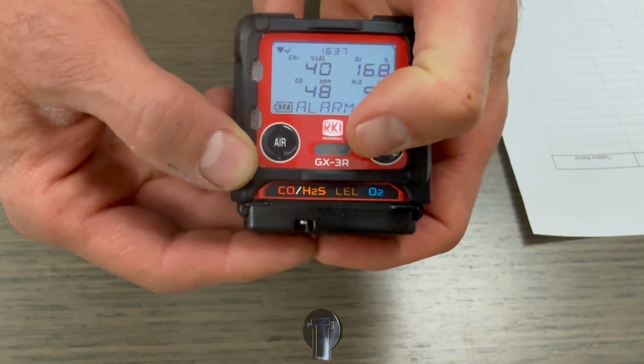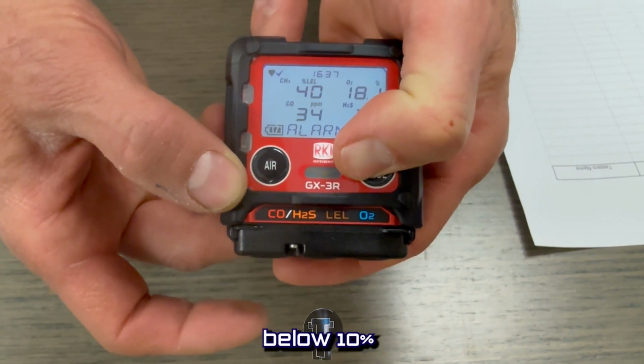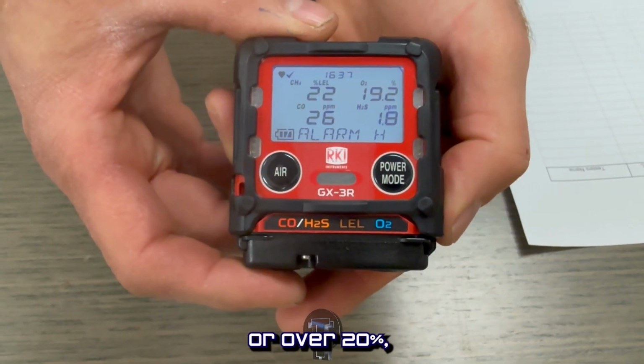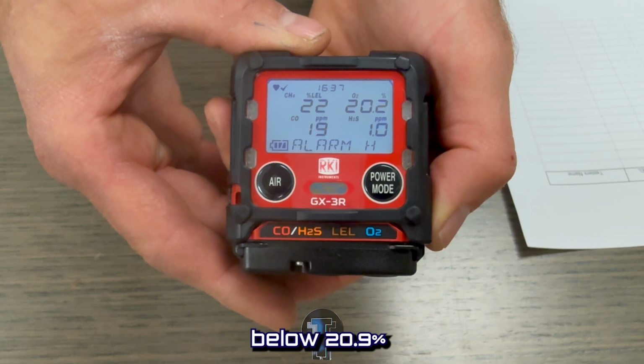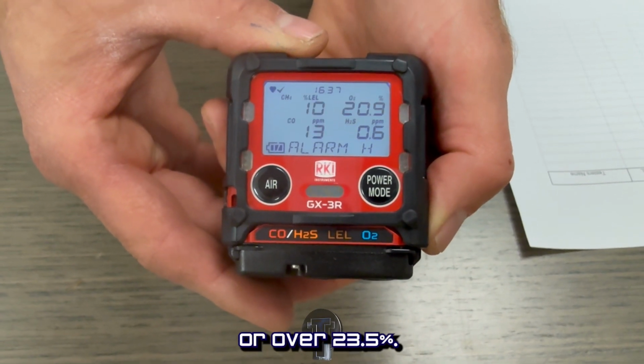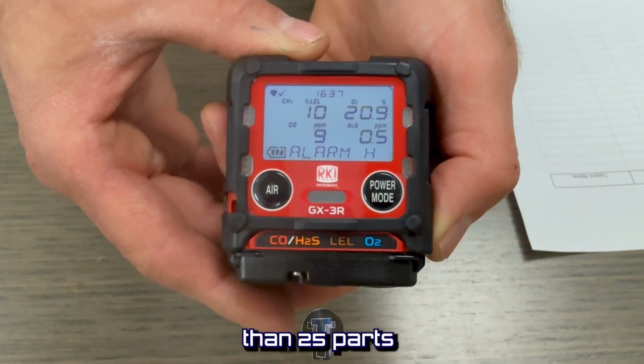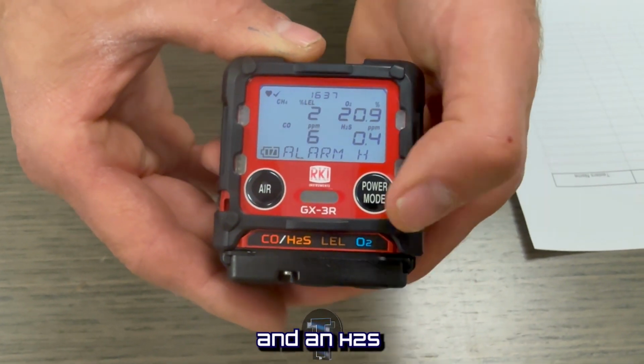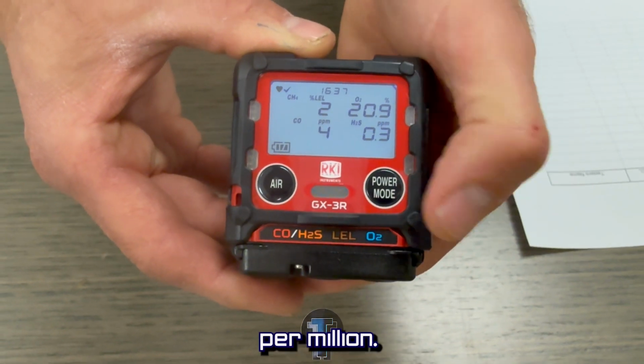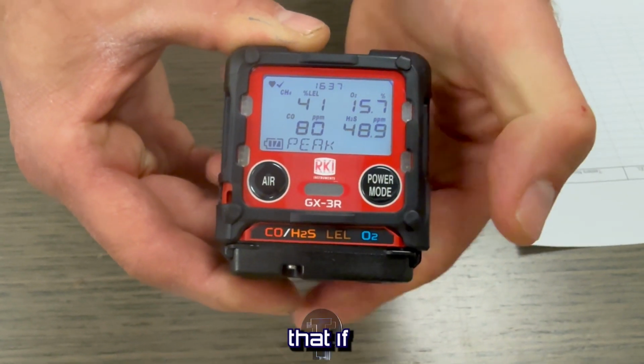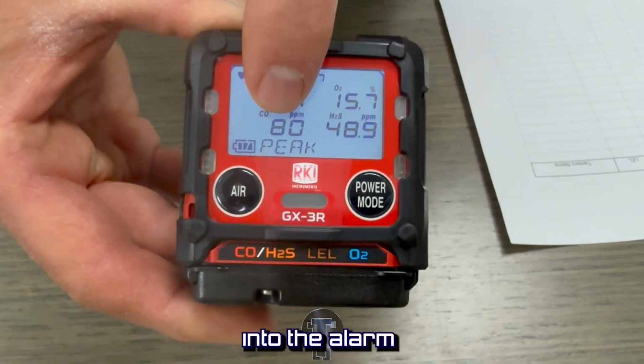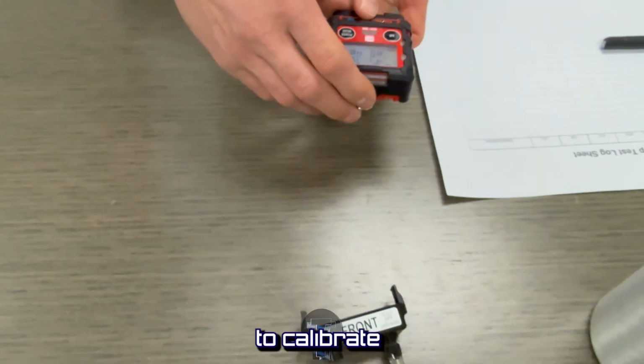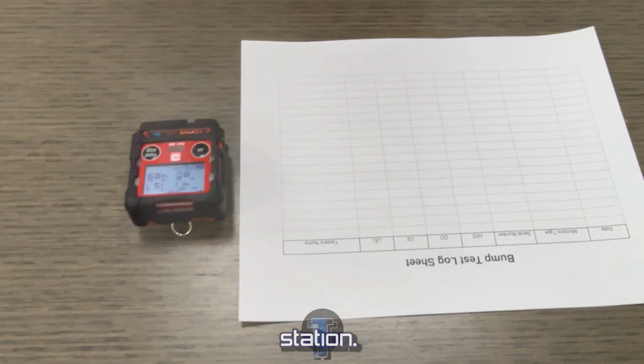The bump test alarm condition will show the LEL reading below 10% or over 20%, the O2 reading below 20.9% or over 23.5%, the CO reading greater than 25 parts per million, and an H2S reading greater than 10 parts per million. It is important to note that if the personal gas monitor does not go into the alarm condition, you will need to calibrate the monitor using the docking station.